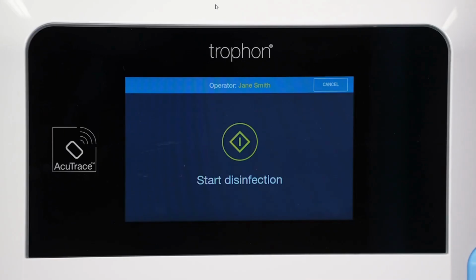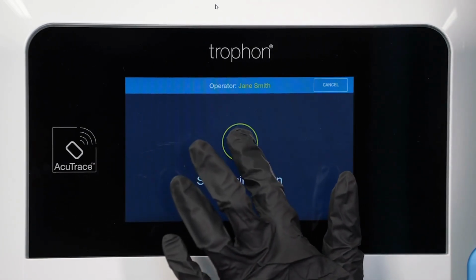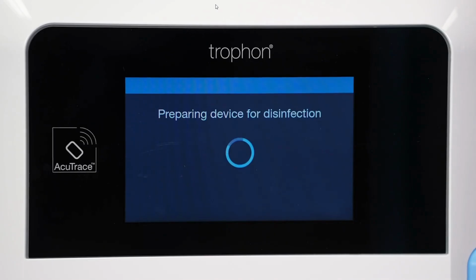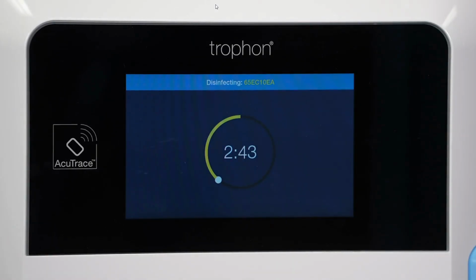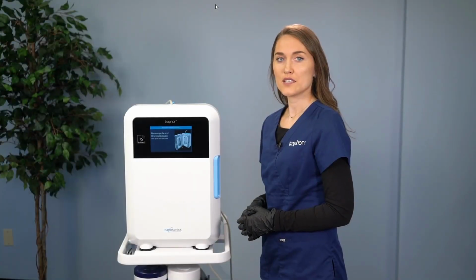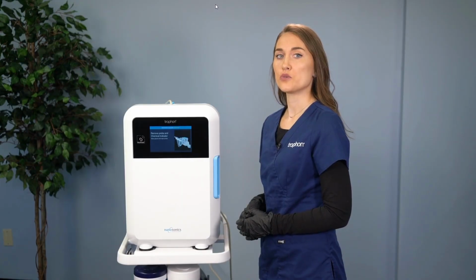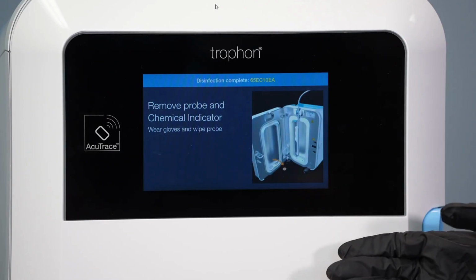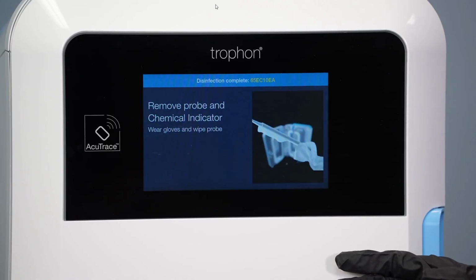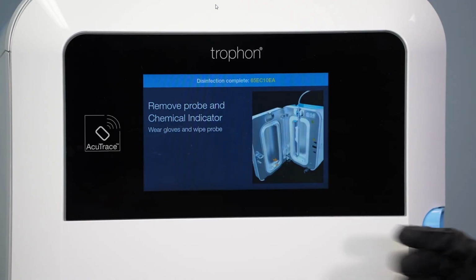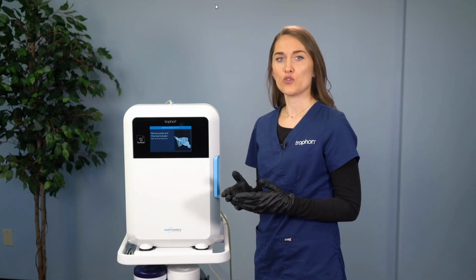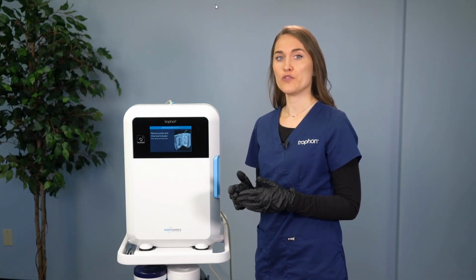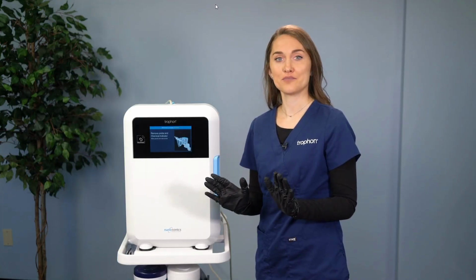You'll notice that the door closes on its own before the cycle begins. Push the button right in the center of your screen to start your 7-minute disinfection cycle. Once your cycle is complete, your screen is going to take you through some prompts. Right now, it is telling us to remove probe and chemical indicator, wear gloves, and wipe probe. So at this time, you'll want to make sure you perform hand hygiene before donning a fresh pair of gloves.